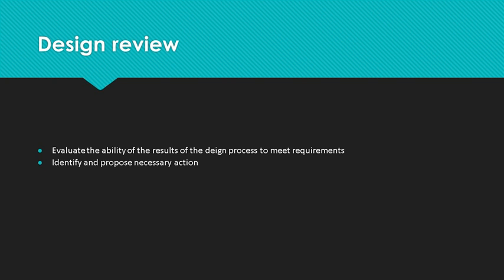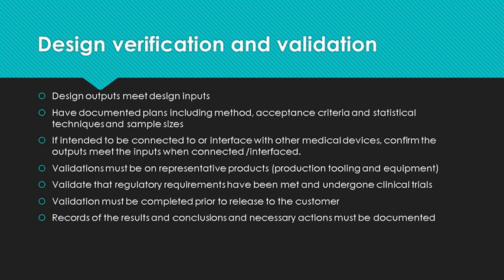In the design reviews and at the completion of the project, the design must be verified and validated. The purpose is to ensure the design outputs have met the design inputs. The verification and validation must demonstrate that the design outputs meet the design inputs. They must have documented plans including method, acceptance criteria, and statistical techniques and sample size for the verification and validation.